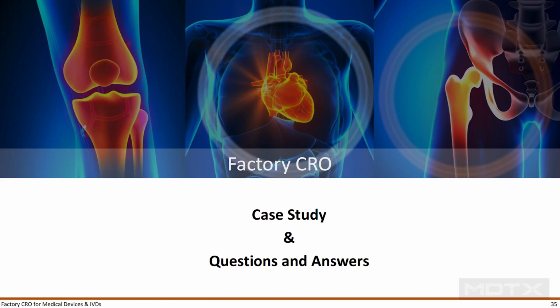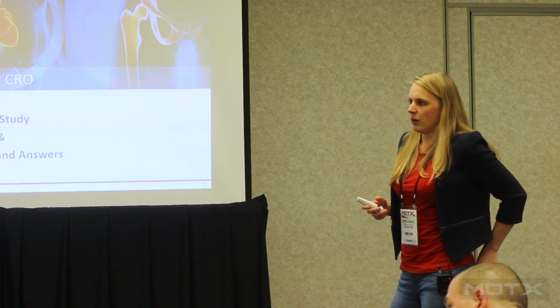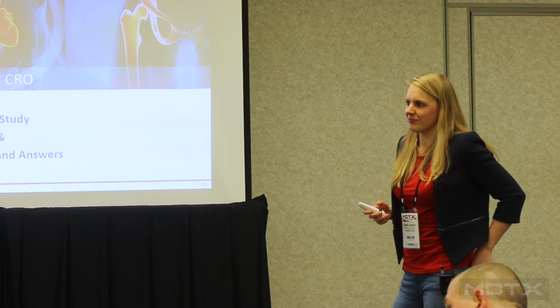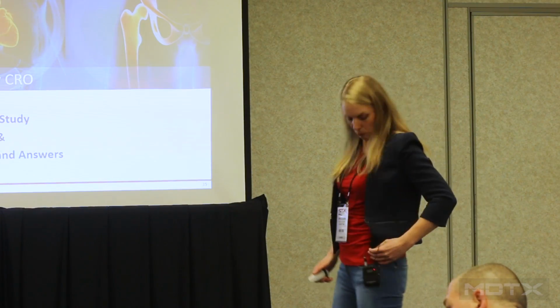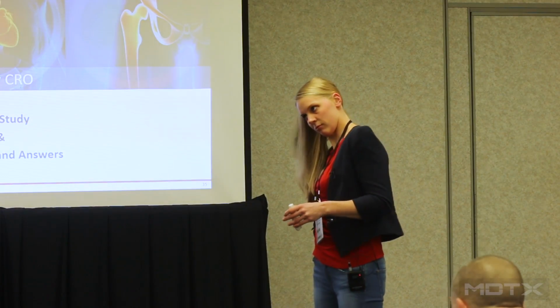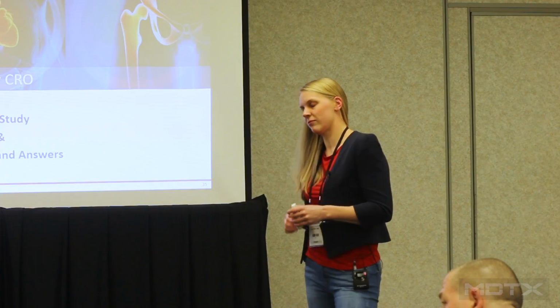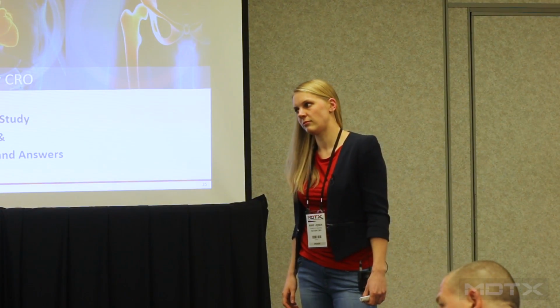Good question. I think that's a very complex topic, because I'm not sure in the details how it's going to work under the MDR, but in the U.S., if you expand your indications, you have to update your 510(k). So that's a risk that you have to take. You want to take that opportunity to market that indication, great. There's a cost. Are you ready to meet the burden of that, and can you support it in your risk management documentation and in your clinical evaluation, and come out with the same conclusion of safe and effective, or safe and performing as intended?